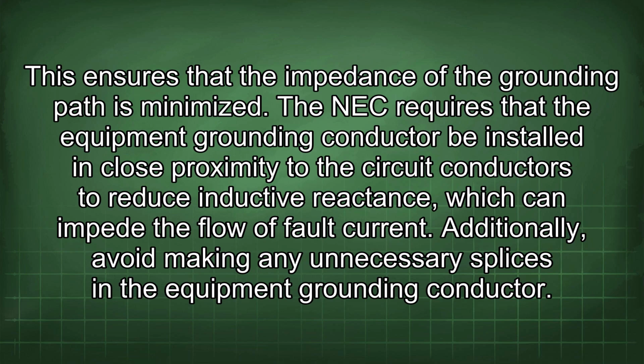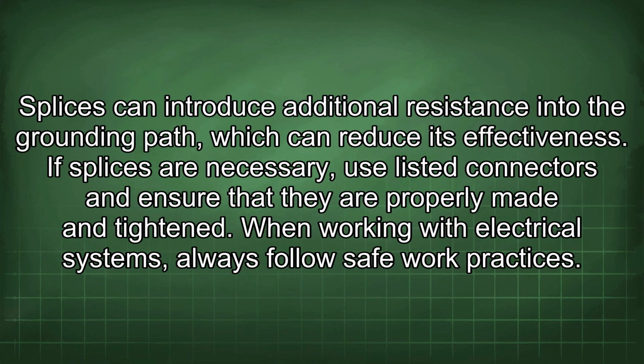Additionally, avoid making any unnecessary splices in the equipment grounding conductor. Splices can introduce additional resistance into the grounding path, which can reduce its effectiveness. If splices are necessary, use listed connectors and ensure that they are properly made and tightened.